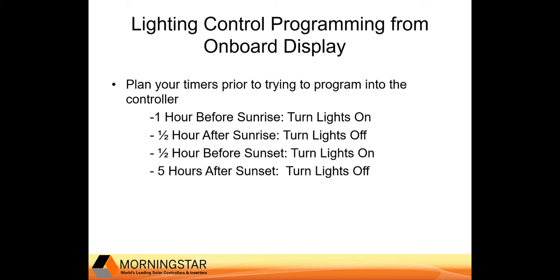In our example, we're going to have the lights come on in the morning prior to sunrise and then turn off again shortly after sunrise. This is a pretty common application — the lights will be on in the morning when you're getting up, and then when the sun comes up, you don't need the lights on anymore so it turns them off. Then in the evening, we're going to have the lights turned back on just before sunset and have them remain on several hours after sunset. Note: it's important that you do a load analysis to ensure you have a properly sized system to run the lights for the amount of time you program into the controller; otherwise, you'll be discharging the battery and eventually go into an LVD situation.